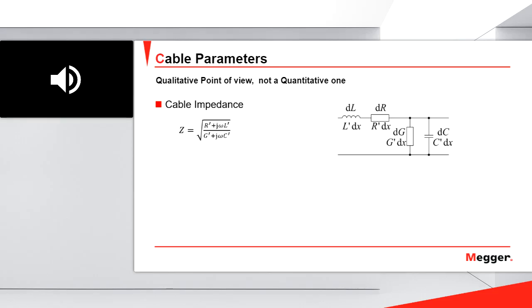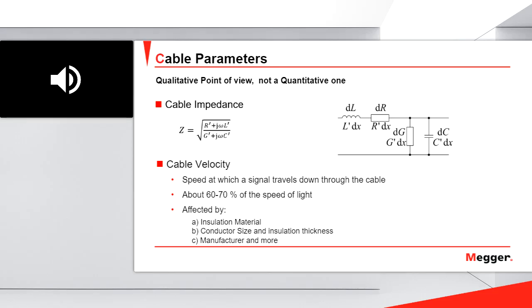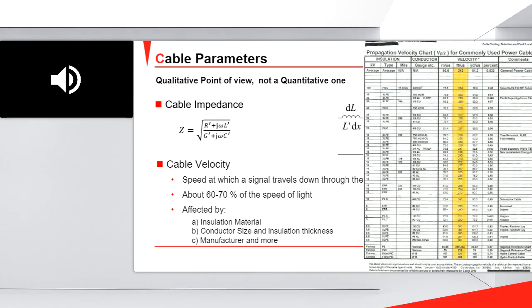The other parameter that is very important is the cable velocity, or the propagation velocity of my cable. When we do the prelocation with the TDR, we send a low voltage pulse through the cable, and we need to know the propagation velocity of the low voltage pulse. Typically, the propagation velocity is about 60 or 70% of the speed of light. Of course, we have tables in which we can see, depending on the insulation of the cable, the size of the conductor, and the voltage, the different propagation velocities.